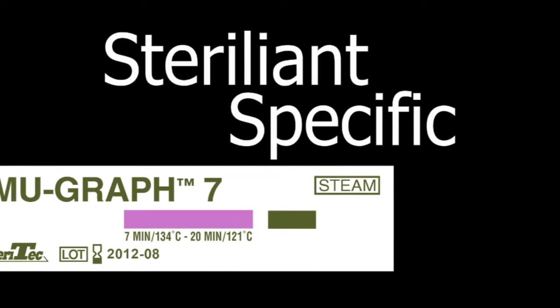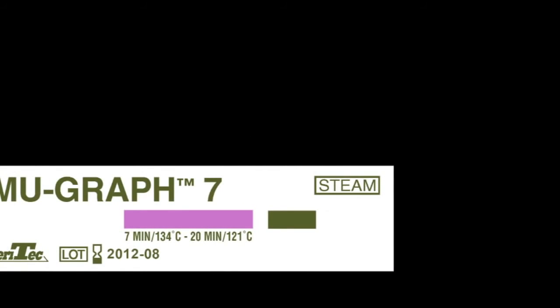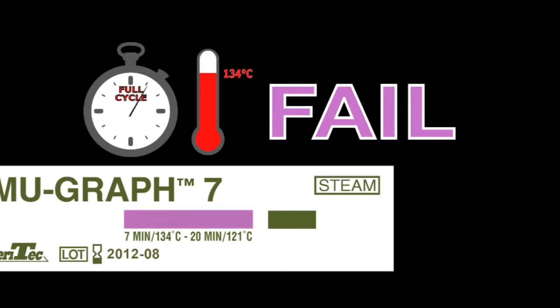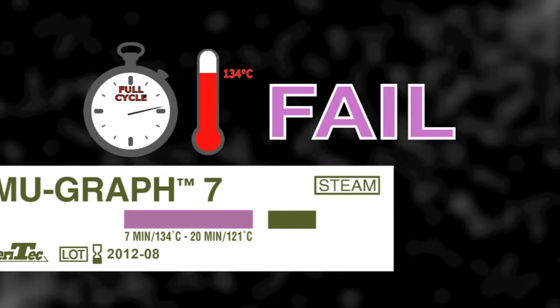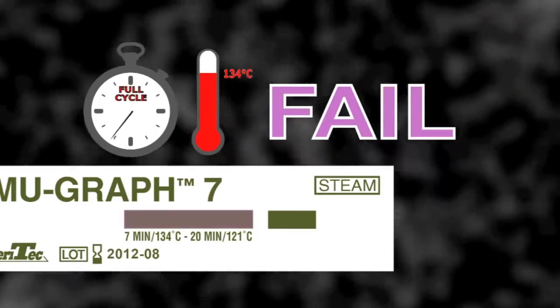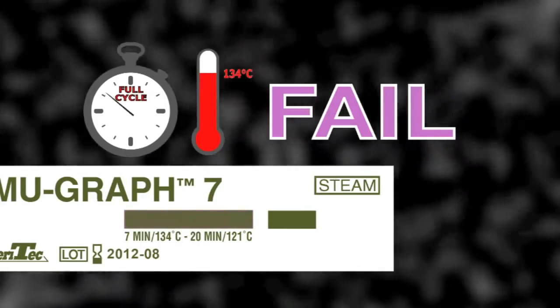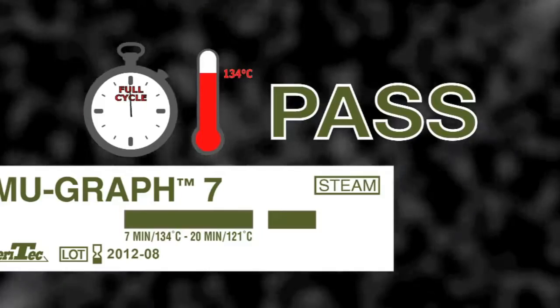When using a steam autoclave to sterilize instruments, the process requires enough time, temperature, and the single most important ingredient necessary for proper sterilization, steam. Dry saturated steam provides the energy necessary to kill germs on the instruments being sterilized. As this hot steam condenses on the instruments, the energy is transferred and destroys microorganisms. Without this steam, sterilization is a much more time-consuming process, and it is significantly less effective.